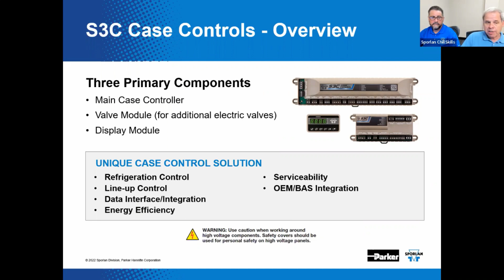From an electrical point of view, we've got an external DC power supply, which must be of a certain class. It's class 2 rated. There's a specification for a maximum wire length between the power supply and the case control, and that's 400 feet, depending upon the gauge of the wire. I think we specified that at 22 AWG. Correct. And you think about it, 400 feet is actually quite a long distance. It gets you quite a ways out there, even in a pretty large store. You wouldn't think you would ever have a need to exceed that, but I guess there's a possibility that might come into play. And we'll talk about in a future episode how to deal with that.